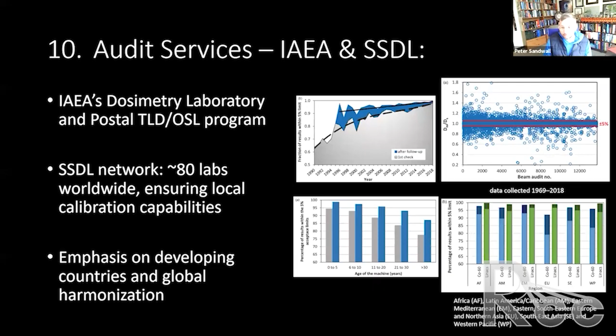calibration errors. You see here in this bottom right corner, and these are showing the percentage of results within 5% limits in the different regions. And what you see, and this was surprising to me, is that the cobalt 60 units are actually calibrated incorrectly more often than the linear accelerators. This was a really surprising thing to me. And I will share a vignette about something like this that occurred. But it's interesting. So again, just things to be mindful of. We think cobalt 60 unit, oh, of course it's going to be calibrated correctly. That's just cobalt, but errors can occur and do occur.